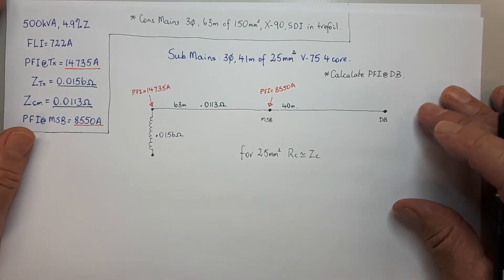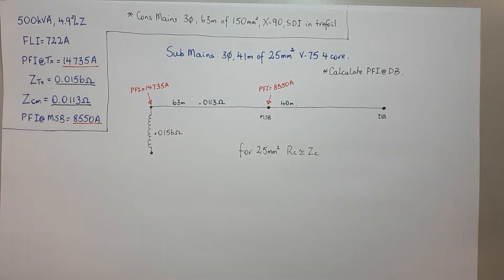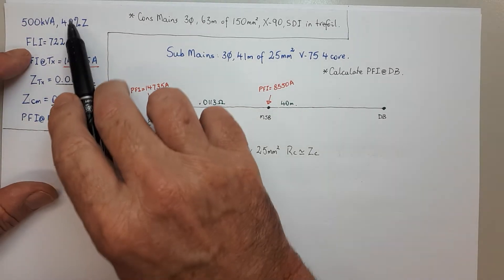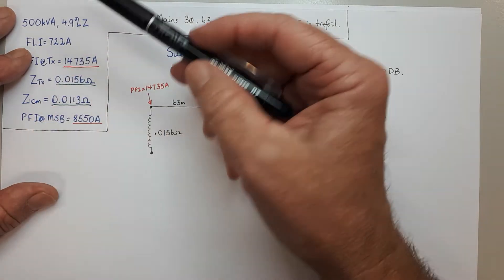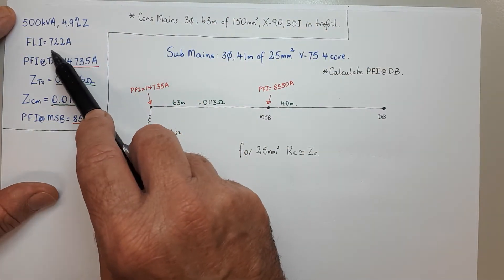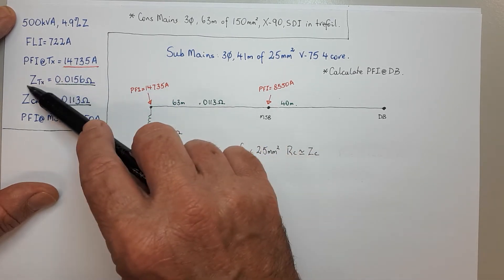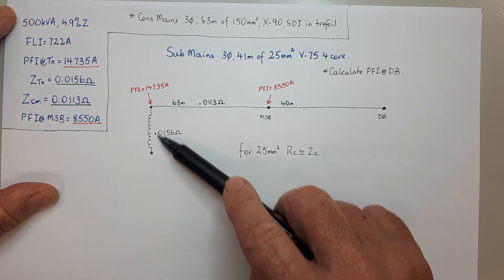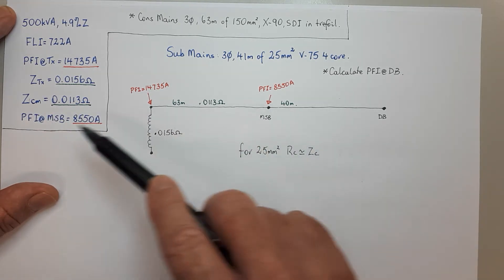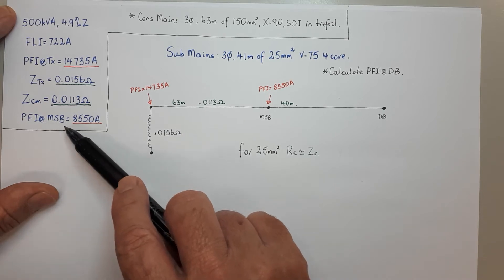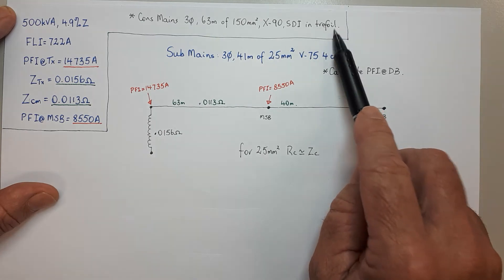Following on from our last adventure with prospective fault current, we worked out all this information: the transformer, the full load current, the prospective fault current at the transformer, the impedance of the transformer winding, the impedance of the consumer's mains which we worked out in the last video, and the prospective fault current at the main switchboard — that's all in here. And that was the consumer's mains that we used.